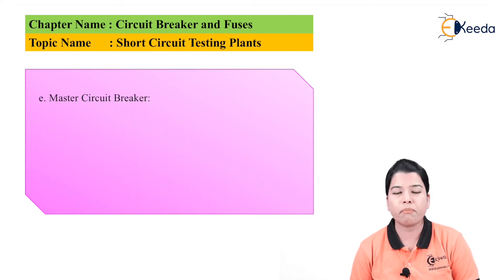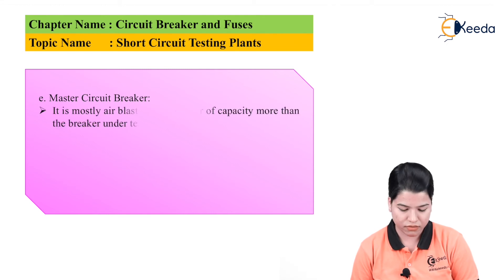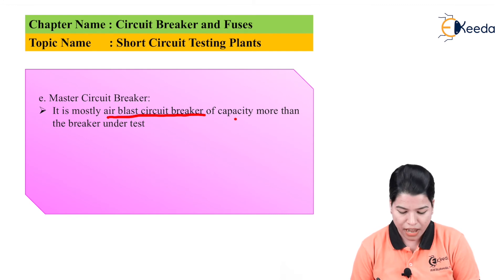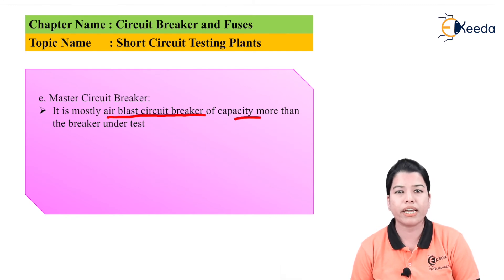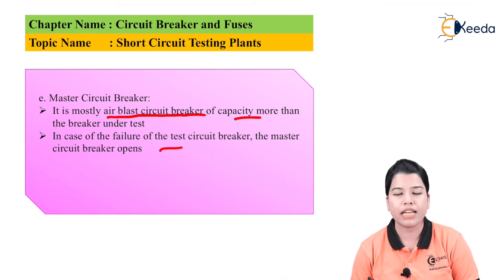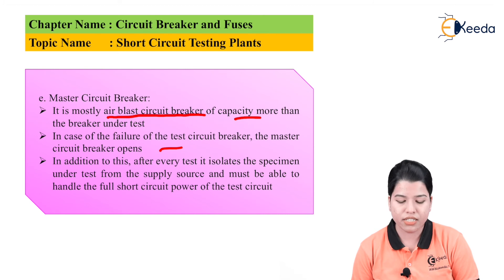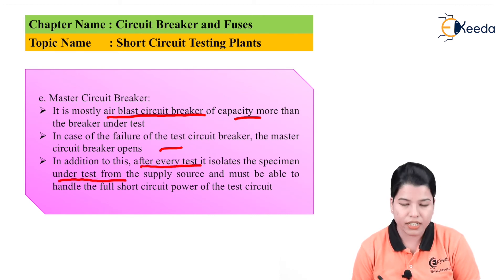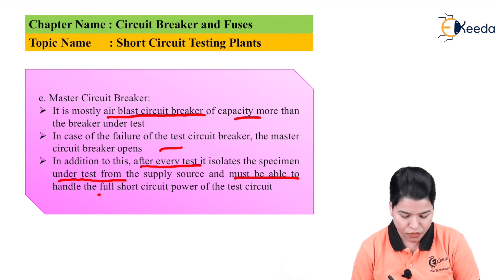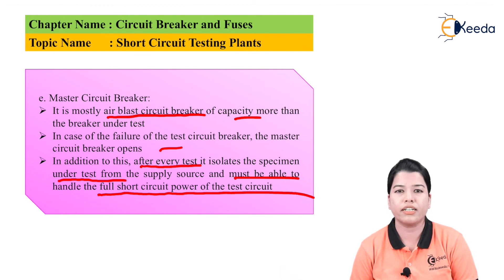The master circuit breaker is mostly an air-blast type with capacity greater than the breaker under test. In case of failure of the test circuit breaker, the master circuit breaker will open and protect the system. After every test, it isolates the specimen under test from the supply source and must be able to handle the full short circuit power of the test circuit breaker.